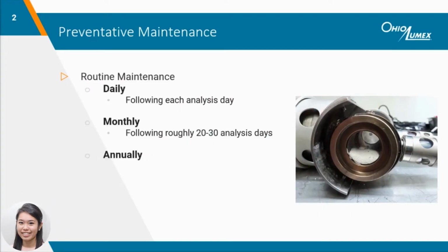Before we jump in, I wanted to touch on the importance of keeping up with routine maintenance and service for your instrument. Preventative maintenance goes a long way, especially to minimize troubleshooting efforts. Taking 15 minutes to clean the analyzer after use reduces excessive buildup of particulate, which could lead to imprecision, poor spike recoveries, calibration issues, and potentially corrosion. Having good cleaning procedures will not only yield more accurate results, but also extends the lifetime of the furnace attachment. Hop on over to the Preventative Maintenance Webinar to check out the latest updates to our recommended maintenance regimen.